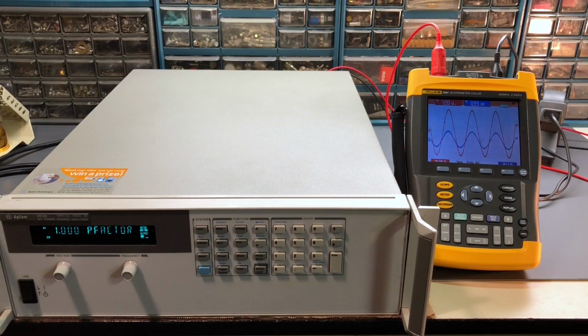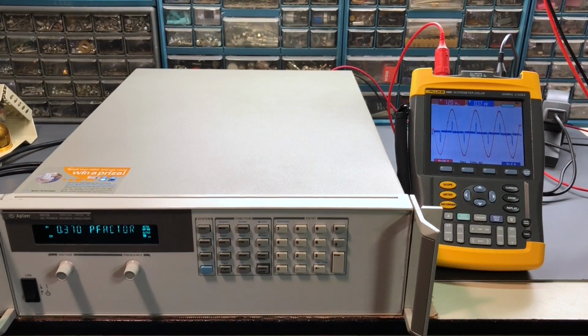So now let me connect something other than an incandescent bulb, and we'll take a look at how the waveform looks on a switch mode power supply as the load on this power source. Alright, for the last example, I have a switch mode power supply connected to the power source. Switch mode power supplies are notorious for causing poor power factors and other issues on the AC line. So let's take a look at this particular model. It's made by Lambda. It's a fairly large switch mode power supply. Outputs 24 volts at over 20 amps capability.